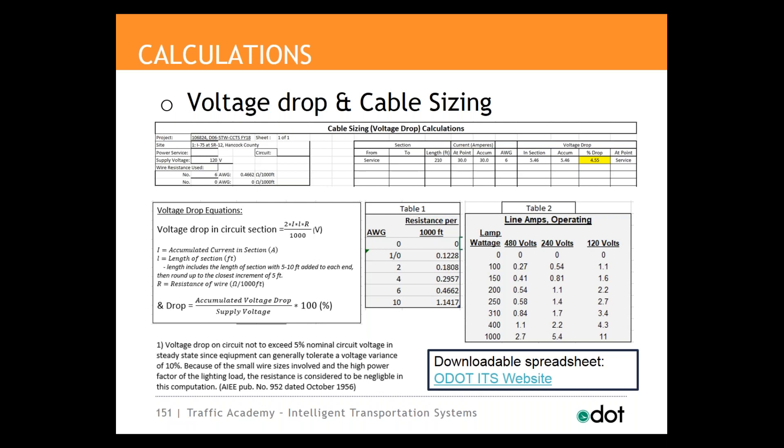ODOT has a voltage drop calculation spreadsheet that should be used to determine the wire sizes. The spreadsheet can be found on the Office of Traffic Operations website. ODOT prefers not to utilize cable sizes greater than 1 AWG, and they will allow voltage drops up to 5%. In the example on the screen, the calculations have determined that the voltage drop will be 4.55% when using a number 6 AWG cable, so a number 6 AWG cable would be used. If you drop down to a 10 AWG cable, your voltage drop would exceed 5%, or you could use a 4 AWG cable to lower the voltage drop percentage, but you'd be paying for a larger cable when it's not necessary.